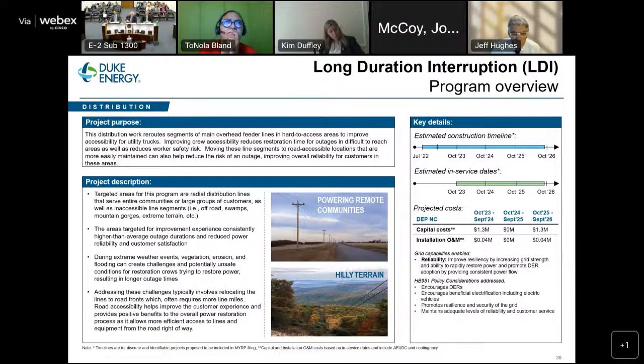The targets in this program are typically radial distribution lines serving large groups of customers or entire communities that tend to be geographically isolated. It doesn't make sense, from a cost benefit standpoint, to build an alternate feed from another direction because of that isolation. So the best solution is to move those lines from inaccessible areas such as off-road, swamps, mountain gorges, or other extreme terrain. These also typically have higher than average outage durations because they're radial and inaccessible, so it takes crews longer to respond, find the problem, and make repairs.